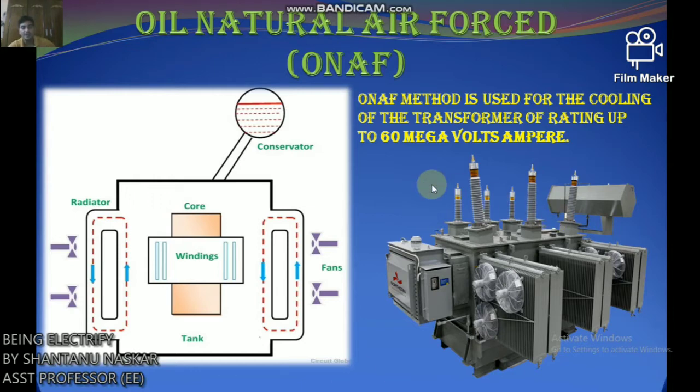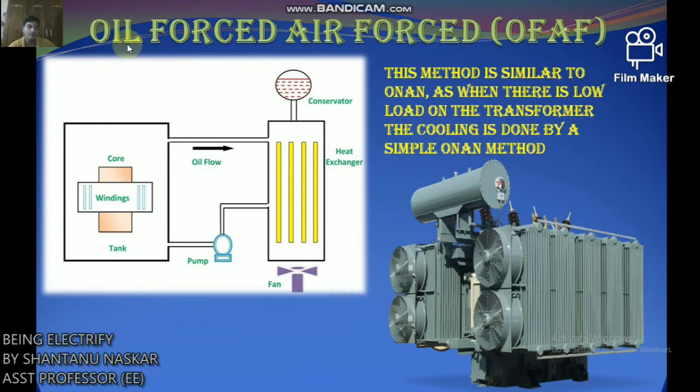Okay, so next we will discuss oil forced air forced, OFAF. As the name itself says, both the oil and the air are applied by force for cooling of a transformer. A heat exchanger is installed through which hot oil is circulated with the help of a pump. Air is forced to pass over the heat exchanger with the help of a high-speed fan.